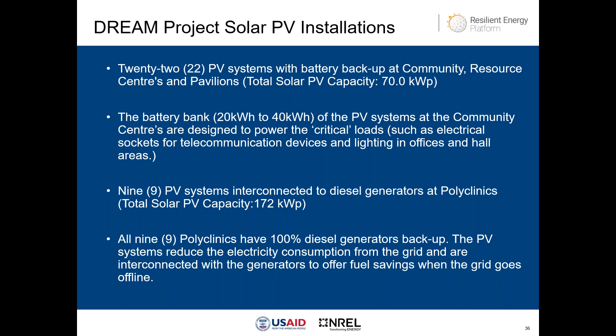The second phase of the project looked at installing photovoltaic systems at all 9 polyclinics on the island. These systems were also hybrid, interconnecting with the diesel generators at the polyclinics, with a total capacity of 172 kilowatts. The polyclinics all have 100% diesel generator backup, so the aim of the project was to allow those generators to have a longer runtime and offer fuel savings. The purpose was not only to reduce electricity consumption at the polyclinics from the grid, but also to allow those generators to run longer in the event of a grid outage.